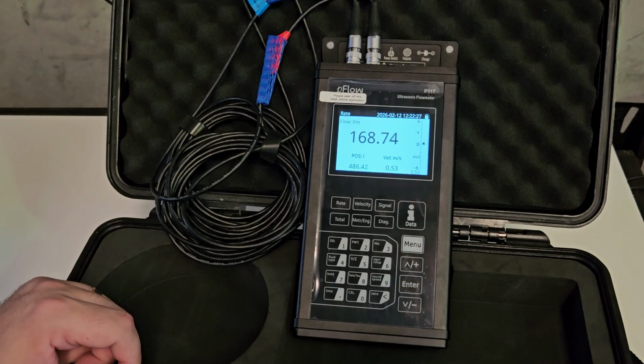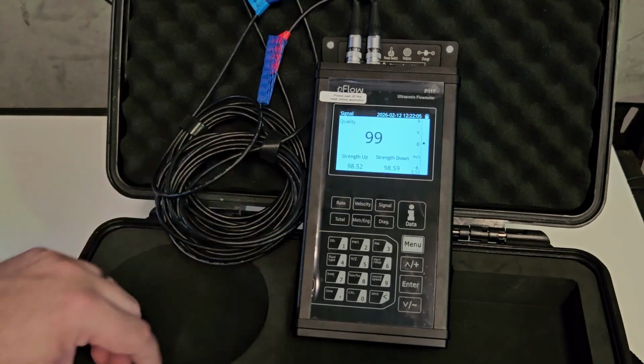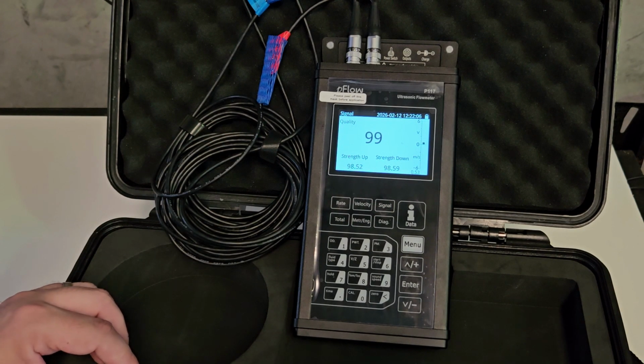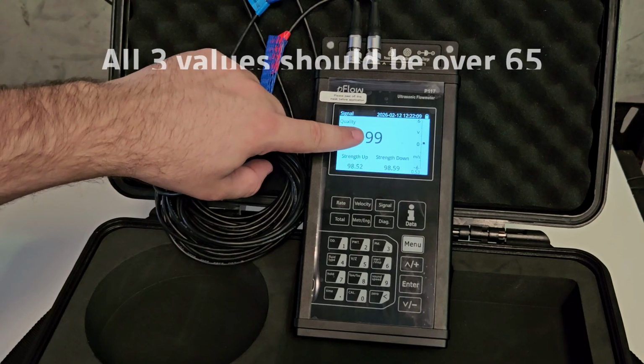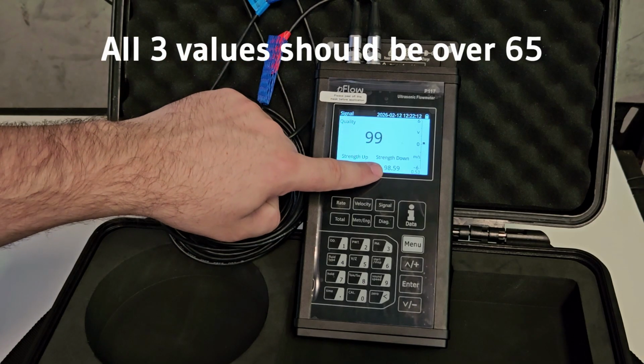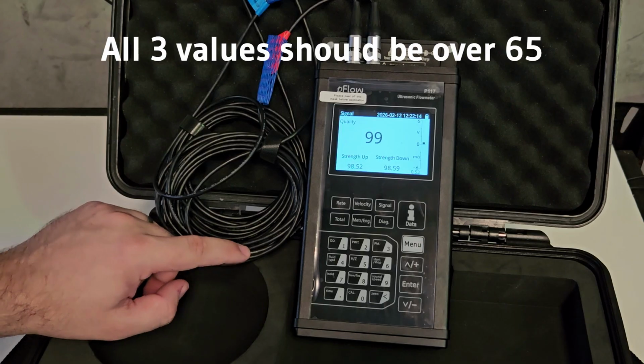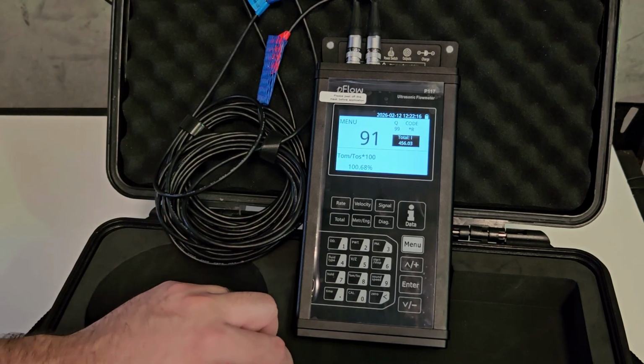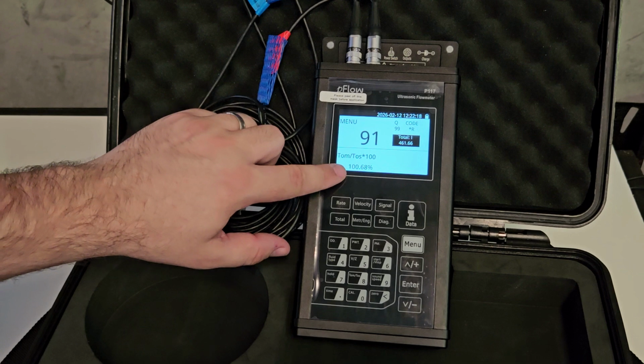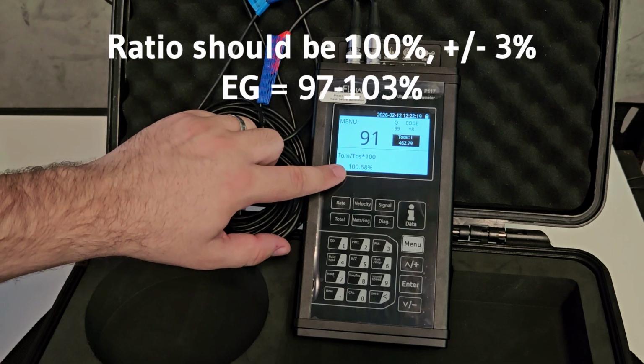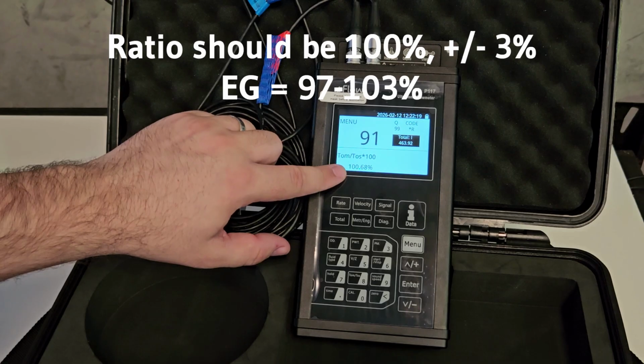If there is fluid flowing through the pipe, it should start measuring. But there are a few key values you need to check to ensure the meter is working properly. First press the signal shortcut. You want signal to be as high as possible. Check these 3 values displayed. In general, signal should be at least 65 or higher for normal operation. Then press the TOS shortcut. This value shown is the transit time ratio. A normal transit time ratio should be at 100% with 3% allowed variance. So between 97 and 103%.